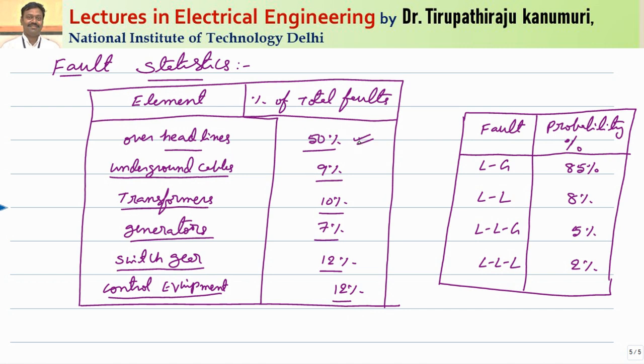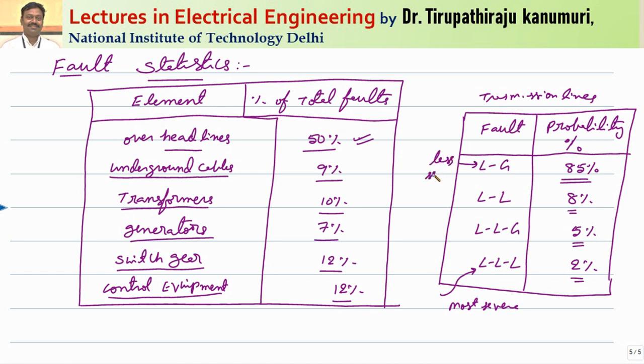Overhead lines have the highest percentage, so more care should be taken for protection of transmission lines. Out of transmission line faults, line to ground faults contribute 85 percent of cases, line to line faults are 8 percent, line to line to ground are 5 percent, and triple line (balanced) faults are only 2 percent. Triple line faults are the most severe but happen very rarely, while line to ground faults are least severe but happen most often, requiring careful protection.